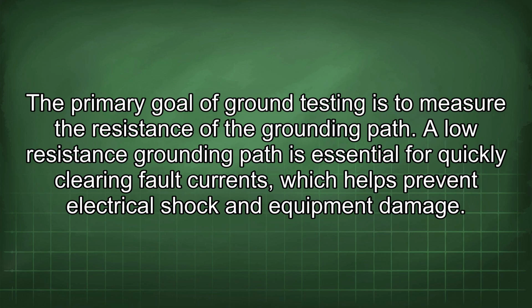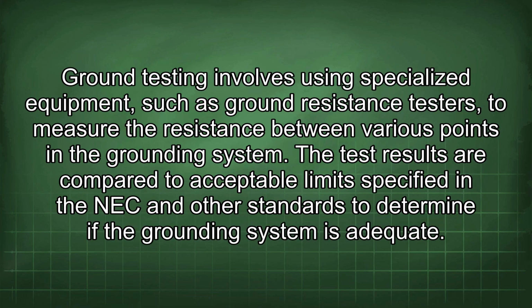The primary goal of ground testing is to measure the resistance of the grounding path. A low-resistance grounding path is essential for quickly clearing fault currents, which helps prevent electrical shock and equipment damage. Ground testing involves using specialized equipment, such as ground resistance testers, to measure the resistance between various points in the grounding system. The test results are compared to acceptable limits specified in the NEC and other standards to determine if the grounding system is adequate.